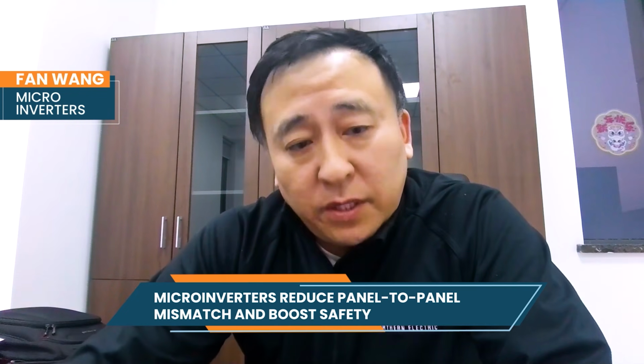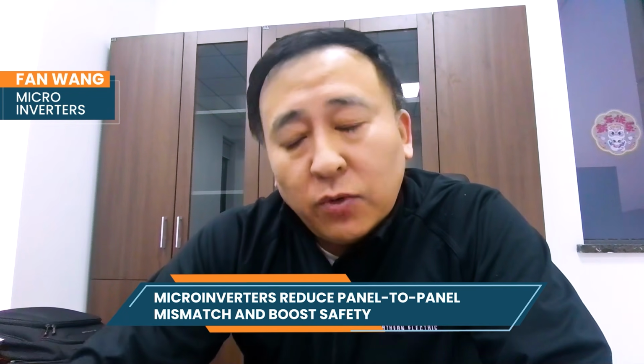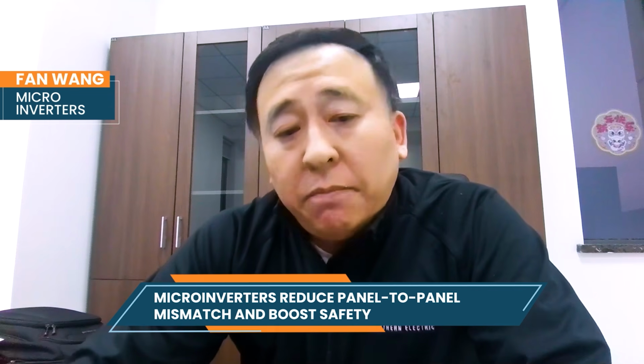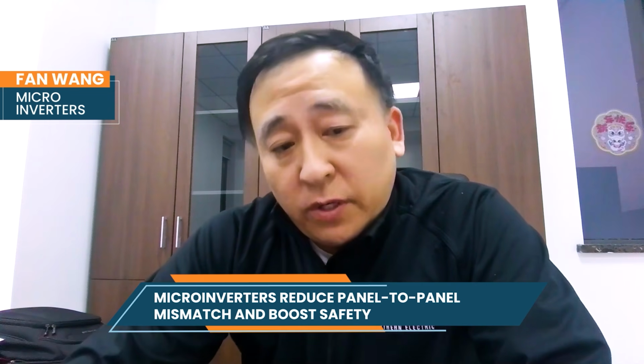There are two reasons. First, there's a mismatch between solar panels. Even if the roof is flat, the solar panels are not identical, so there's a mismatch, and you can still see a little gain from individual power tracking, which gives a little benefit. But I'd say the main benefit of using microinverters is safety. With string inverters, you're going to see 600 volts, 1000 volts, and in some countries even 1500 volt DC voltage. That's very risky on the roof. So even for a flat roof, the biggest advantage of microinverters is safety.